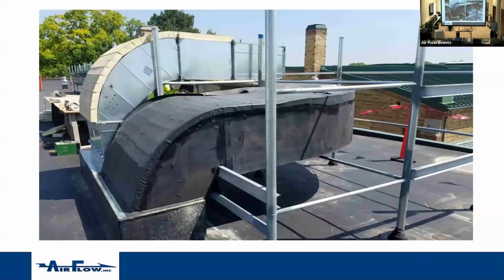All right, this is a consulting engineer sent me this picture. This is a great picture. Why is it a great picture? It shows the ducts in various stages of being installed outdoors. So when I think of outdoor ductwork, I think of the ductwork's already there. It's wrapped, it's installed, it's on structure, it's insulated, it's got the cladding around it. Okay, so what we see here is, here's how the ductwork starts, just high pressure ductwork, right? And then this insulator is going to come in and lay his insulation over the top. Whatever that insulation is specified as is up to the consulting engineer. And then it's gonna get clad. In this particular case, it's clad with something that I wouldn't normally see. It's clad with some roofing material. In other cases, it's clad with some, this is not that unusual, and we hear about roofing, just we're gonna roof it in.